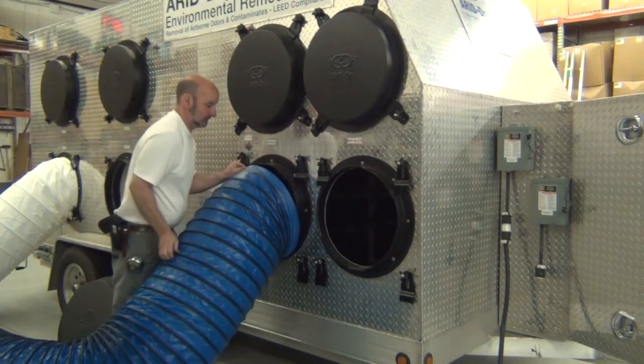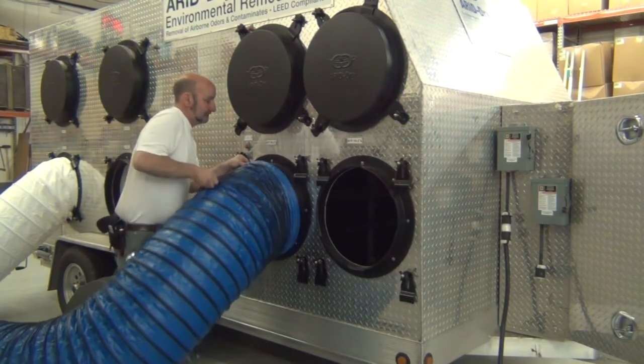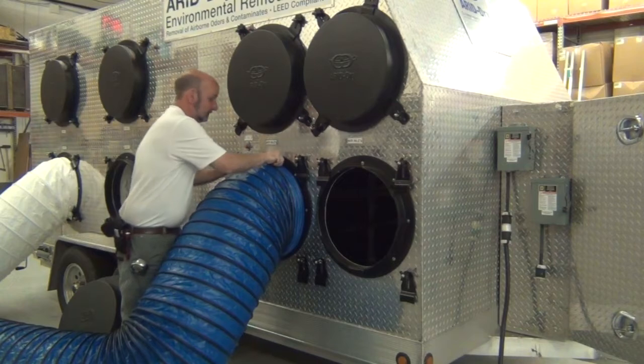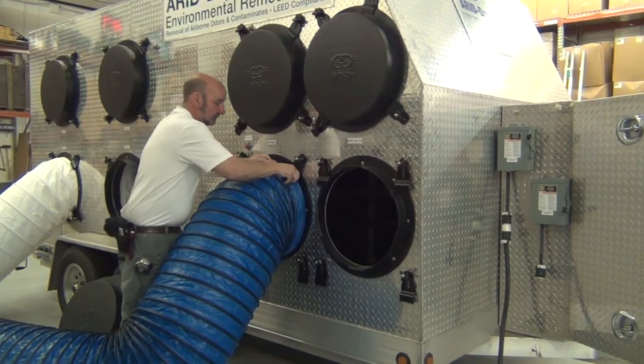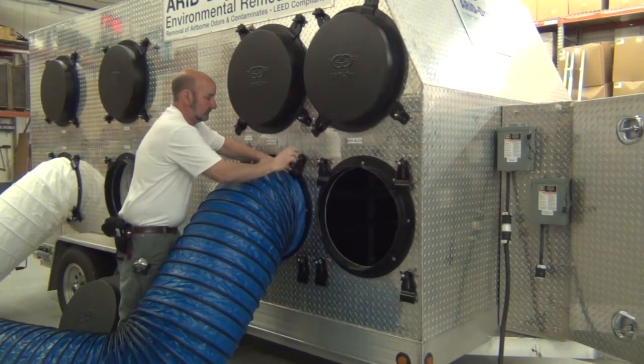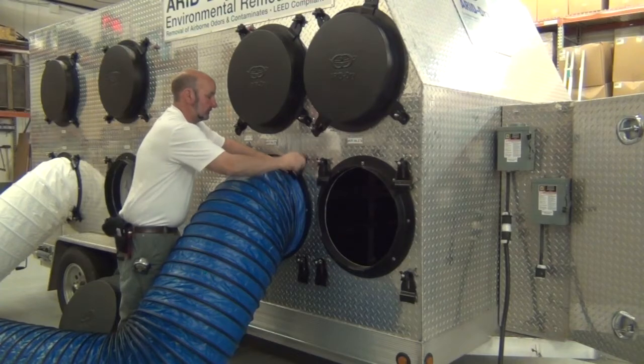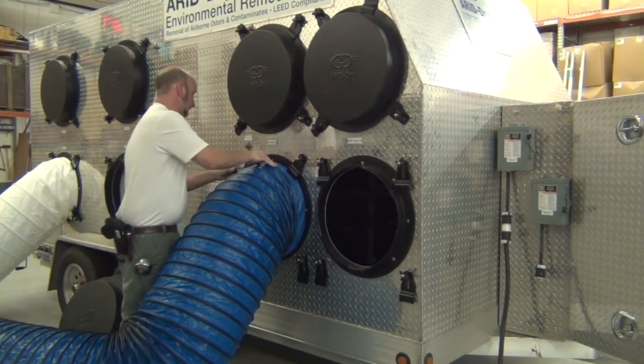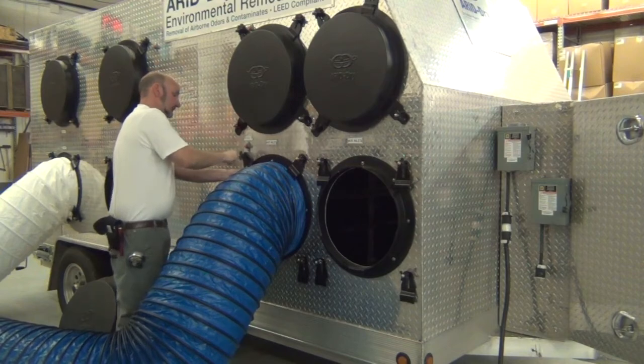Typically the bottom slides on first, and then the top slides up and over the collar, and then becomes fastened with the 4 knobs again, holding the steel reinforcing ring inside the flexible ductwork.